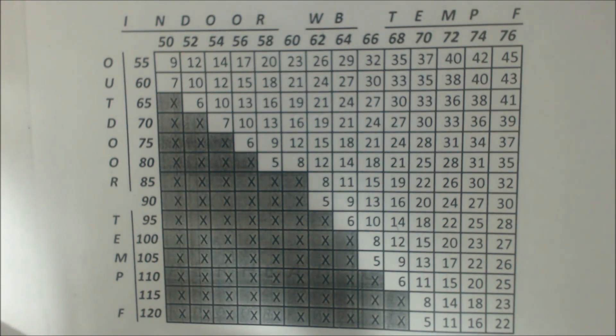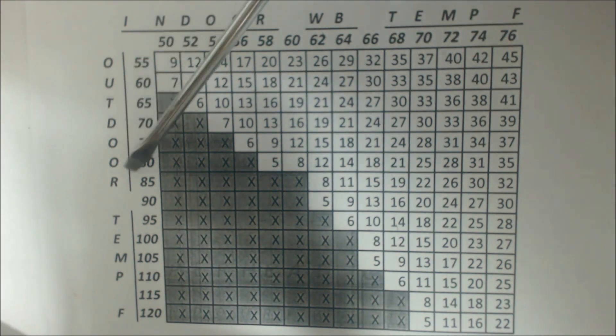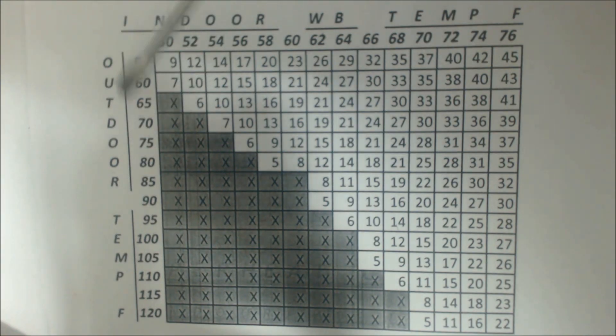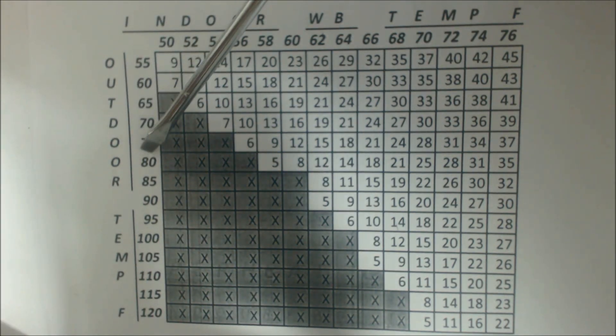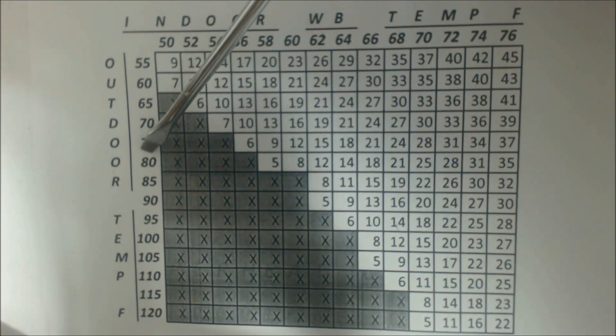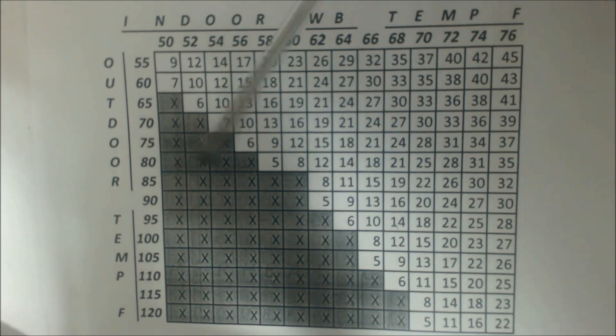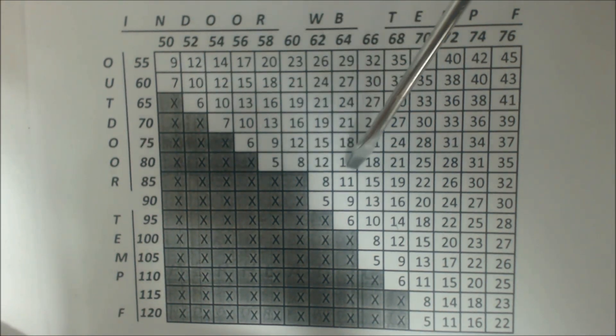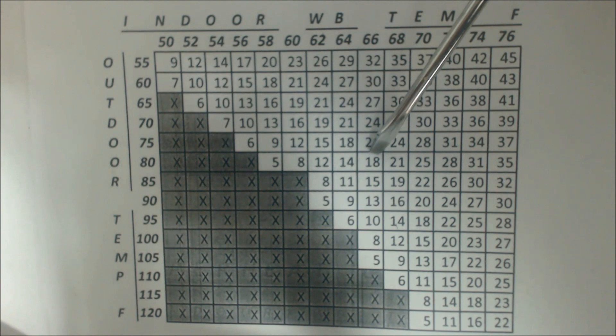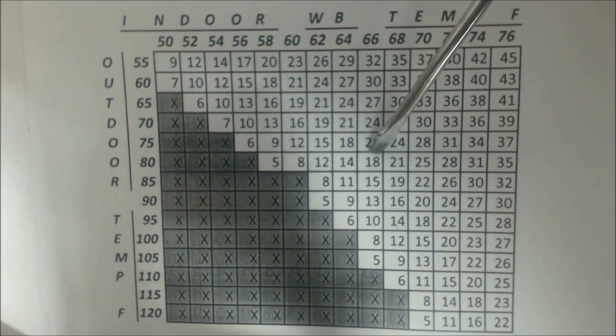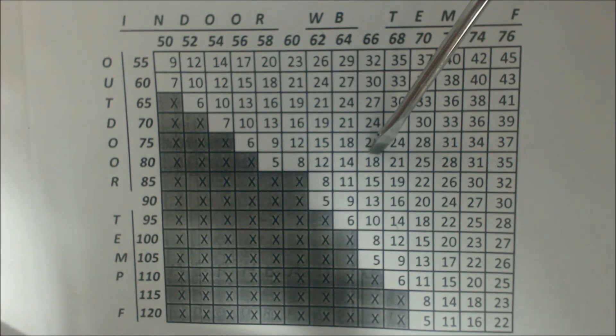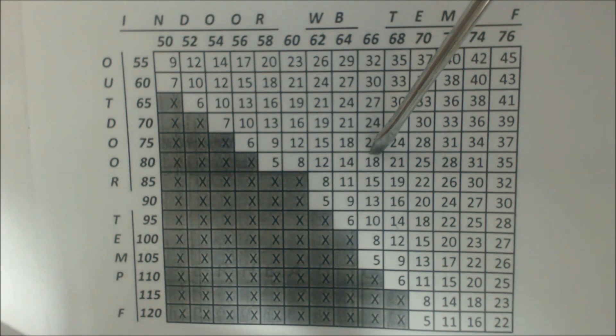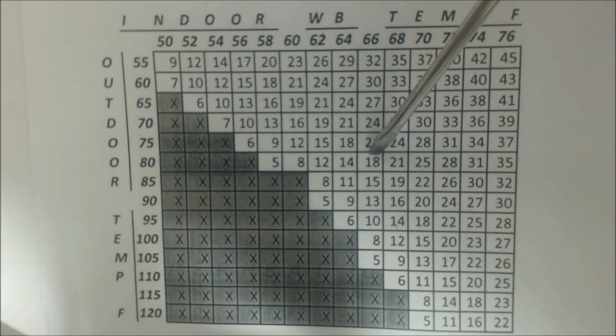Let's just go with another one here. Outdoor temperature of 80 degrees and an indoor wet bulb of 66 degrees. So we're going to follow this 80 degrees over and we find that our target superheat is 18 degrees of superheat.